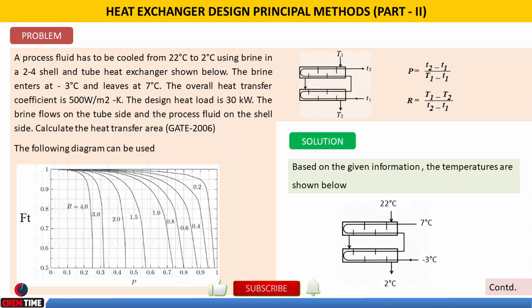In this configuration, the temperatures T1, T2, t1, and t2 are labeled, and we need to identify all four. The process fluid (hot fluid) enters at 22°C, so T1 = 22°C, and it leaves at 2°C, so T2 = 2°C. The cold fluid, brine, enters at −3°C so t1 = −3°C, and it leaves at t2 = 7°C.